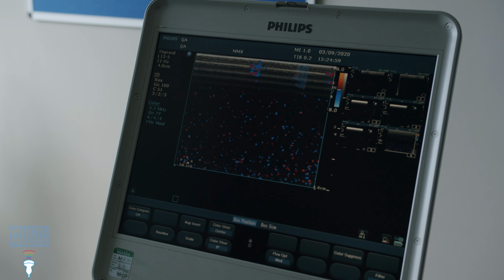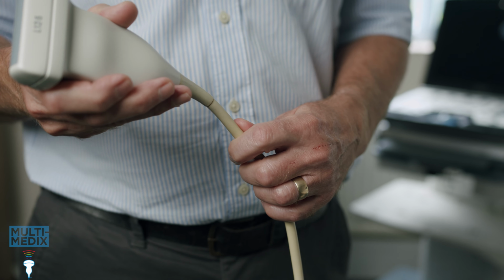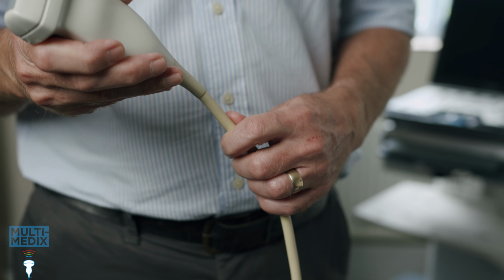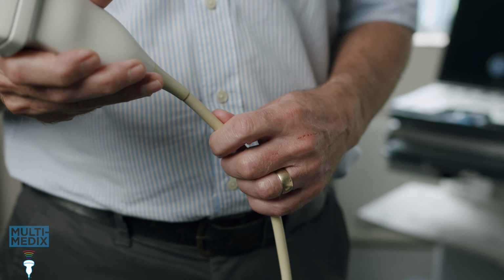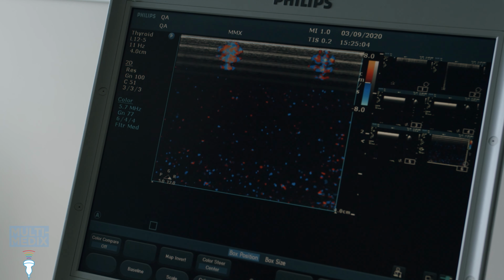Finally, turn on Colour Doppler and expand the colour box to the full width of the image. Increase gain to show slight colour speckling, then flex the cable at the strain reliefs and any point of visible external damage to the cable, looking for streaks of flashing colour.